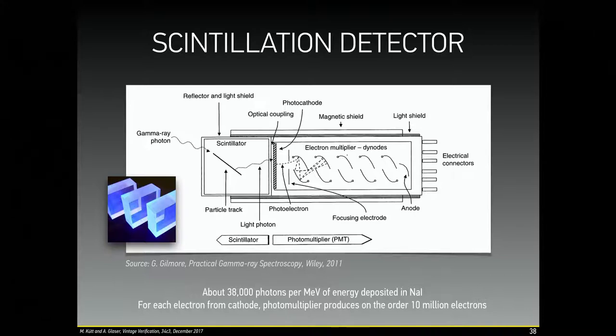So all these photons get emitted in the crystal, and then they hit this photocathode, which sits at the end of the crystal, and they produce electrons. And these electrons then get amplified by something called the photomultiplier tube, which is a tube where the electrons get accelerated from the cathode towards the anode.